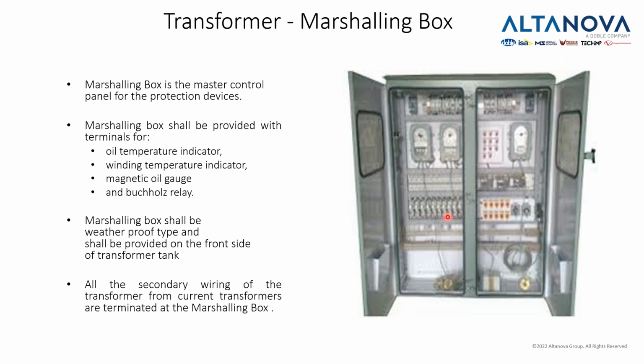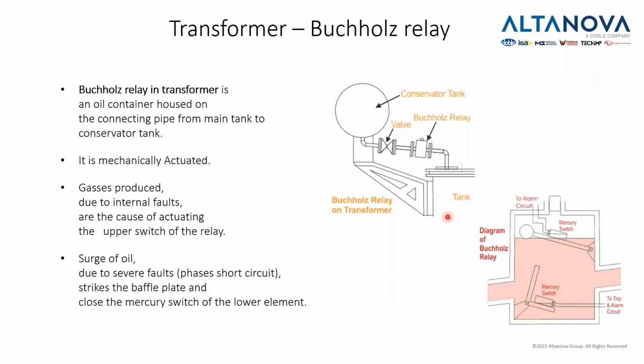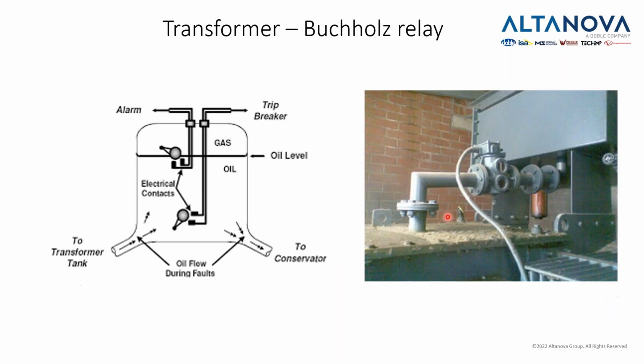All protection, let's say, is connected through this marshalling box. And then we have a Buchholz relay, which will detect if there has been a fault in the transformer and if the oil starts to foam. It will trip its protection, and both circuit breaker and the circuit breaker supplying the transformer will trip.